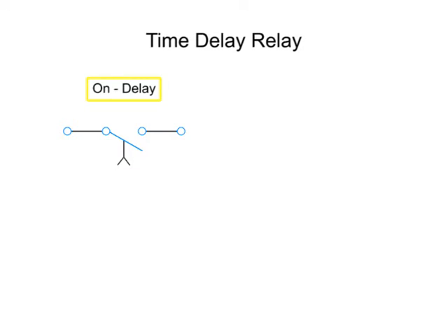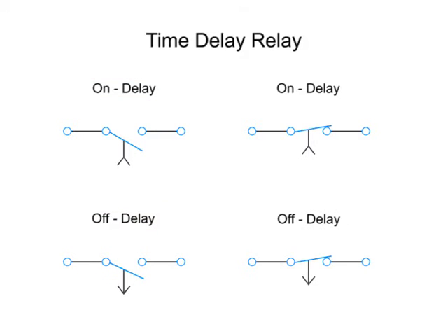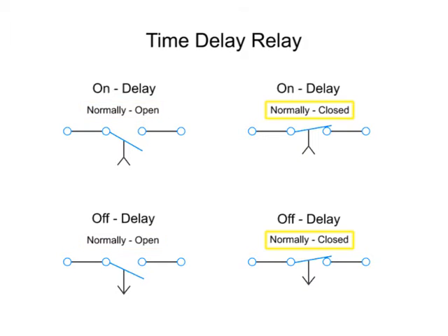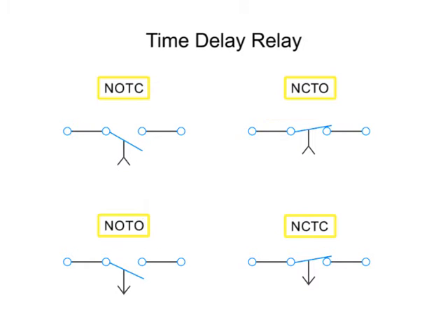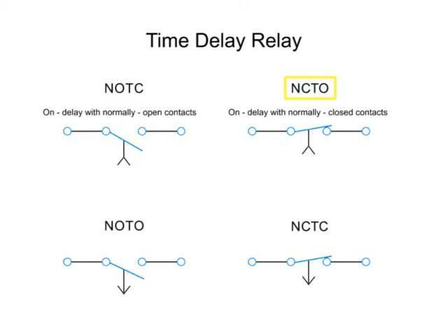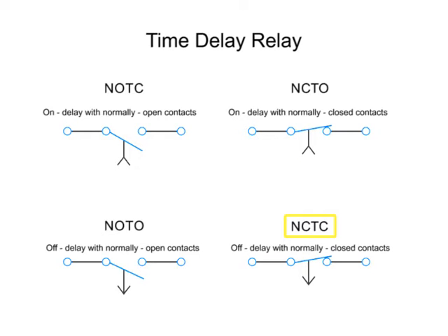Let's look at four basic types of relays. There are two types of relay functions: on delay and off delay, each with two types of contacts — normally open and normally closed — represented here by four symbols. NOTC functions as an on delay with normally open contacts. NCTO operates as an on delay with normally closed contacts. NOTO functions as an off delay with normally open contacts. And NCTC operates as an off delay with normally closed contacts.